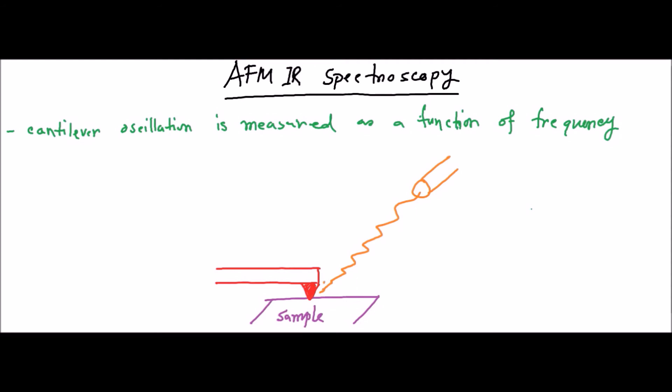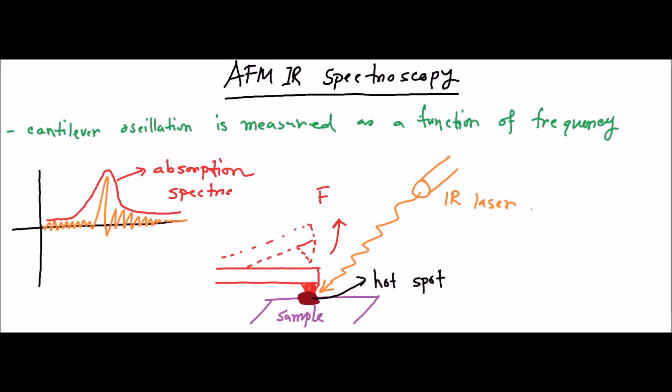In spectroscopic mode, cantilever oscillation is measured as a function of frequency or wave number. The tunable laser emits light with varying frequency or wave number. When the frequency is equal to the absorbing wavelength of the sample, it is absorbed by the sample and the resulting temperature increase causes an instant thermal expansion of the sample at that hot spot. This thermal expansion acts as a force on the cantilever and drives it into oscillation. The oscillation is proportional to the absorption coefficient of the material under observation. Since different materials absorb different wavelengths, the absorption spectra we get from cantilever oscillation is used to identify chemical species.